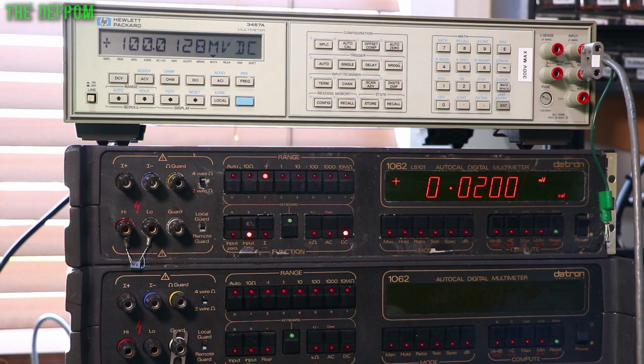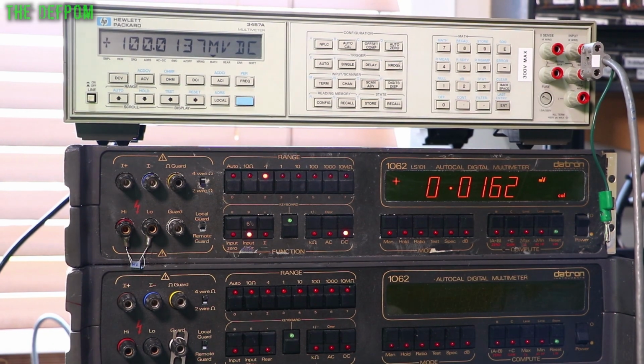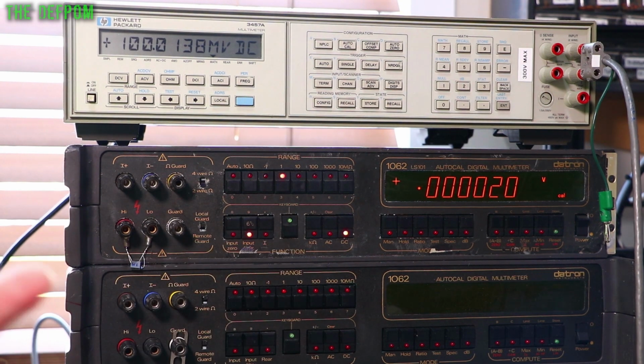Or not. Okay, I got it wrong. I need to be on the 1 volt range. That's why it didn't work. So 1 volt range, then push the linear button. Here we go. This will take about 20 to 30 seconds, something like that. And then once that's done, we swap over and put in a 10 megohm. And it's already done that one. That's pretty quick.